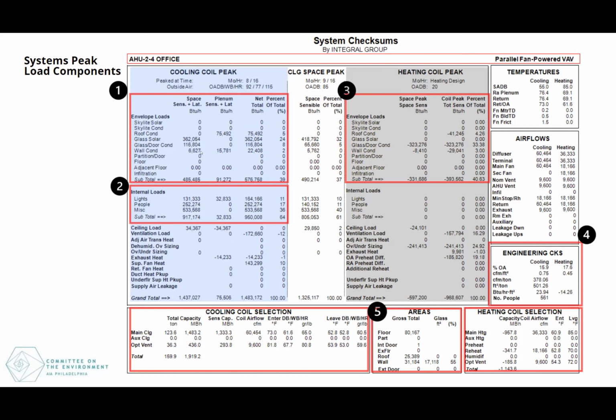time. Here, right away, what I would draw your attention to is what is the total here. So the total of the envelope is 485,485, whereas this one is 917,174. So what this tells me is the system is serving a space that is internally load driven. So these are some important items to look at. I would also be looking at the total area to see whether it is justified that this is the area. Sometimes the areas are off. It shows whether there is roof, there is wall modeled. So these are important checks that any energy modeler would do. And these are some really common sense checks, along with the CFM per square foot and CFM per ton.